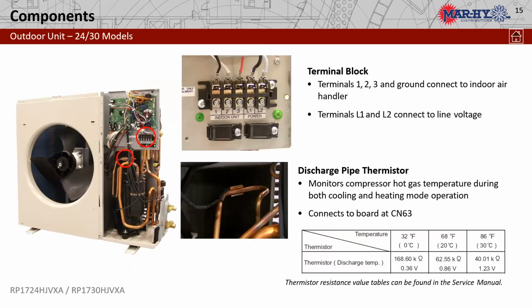So as we look at the outdoor unit on the 24 and 30, that looks very familiar to me. 1, 2, and 3 to the indoor unit, with line 1 and line 2 as our main power. So this should be familiar to most all of you that does the mini splits, because basically we've got a kind of a hybrid system here with the basic looks of a mini split on the outdoor unit going to our conventional air handler. So you can see too that there is a discharge pipe thermistor. We see that a lot nowadays on any of the variable speed. There is a thermistor there that is not a 10K. I'm not sure what K it is, but there are charts to be able to compare them to actual temperatures found in our service manuals, which we'll cover a little bit of later on.